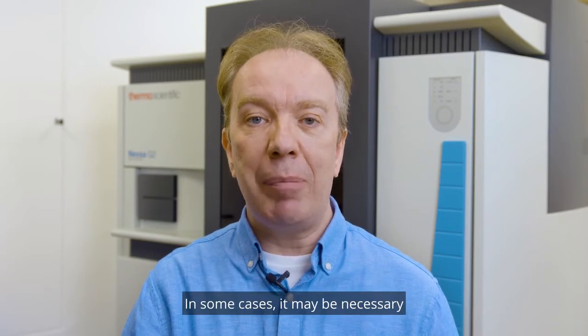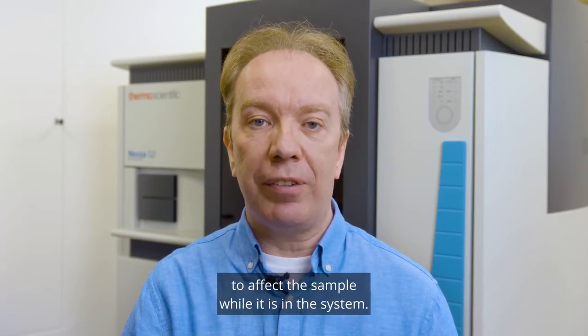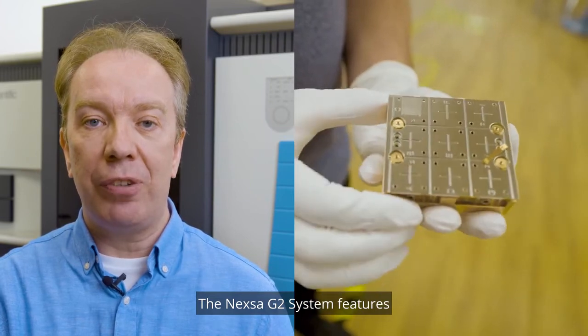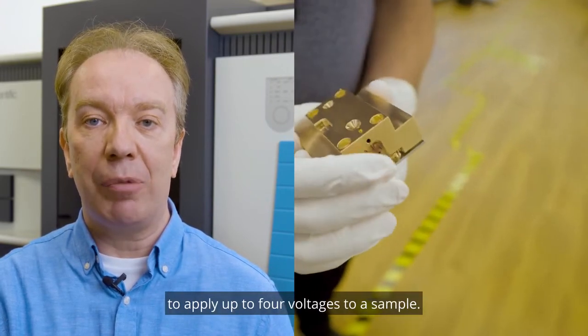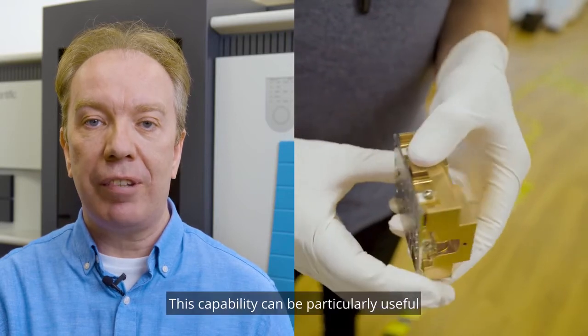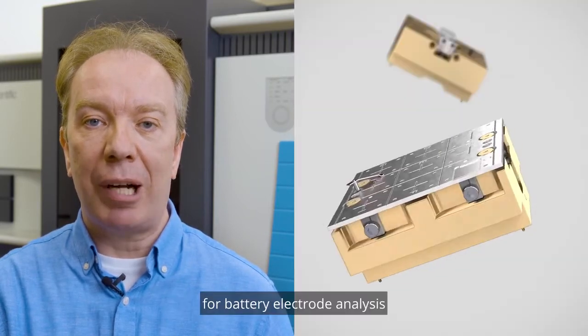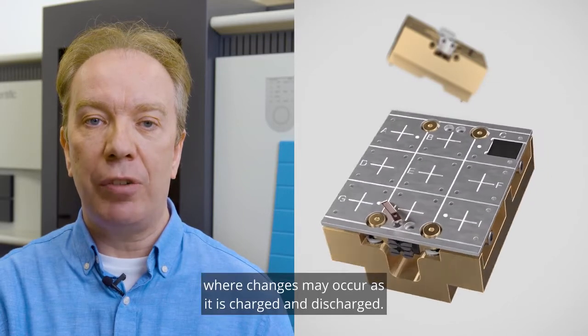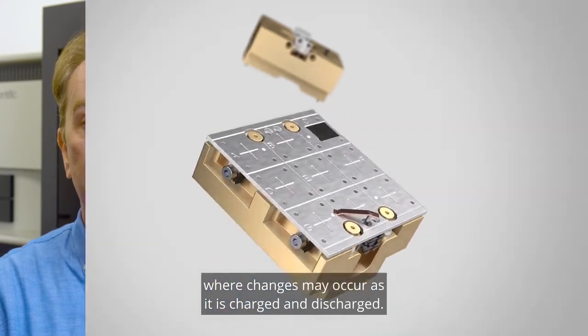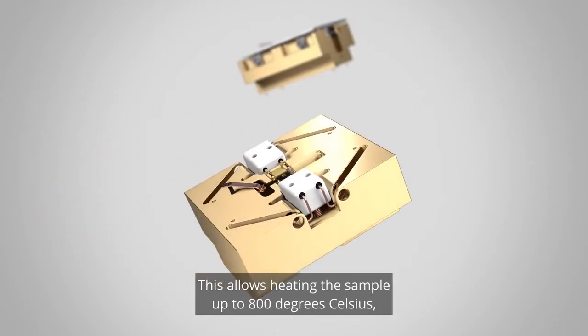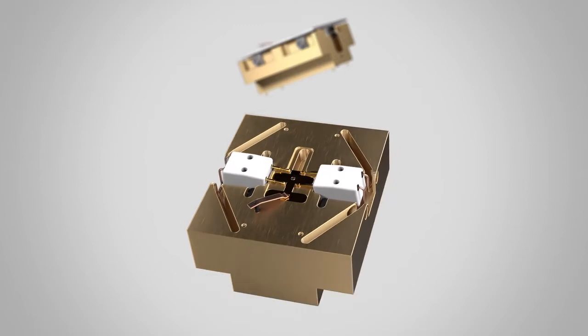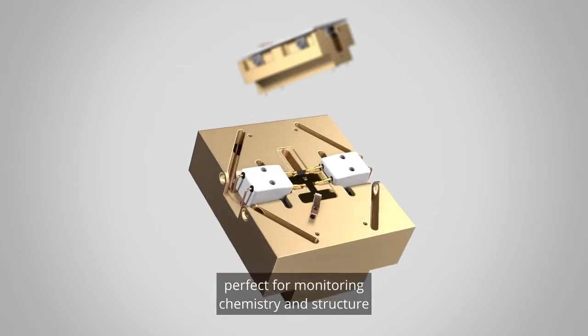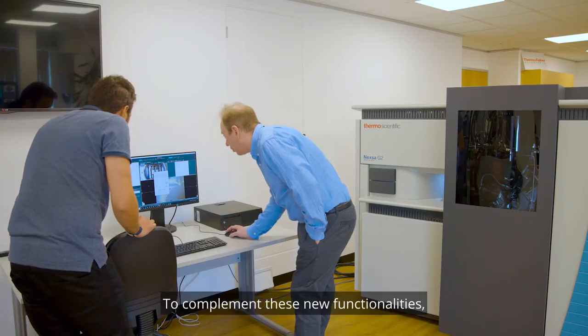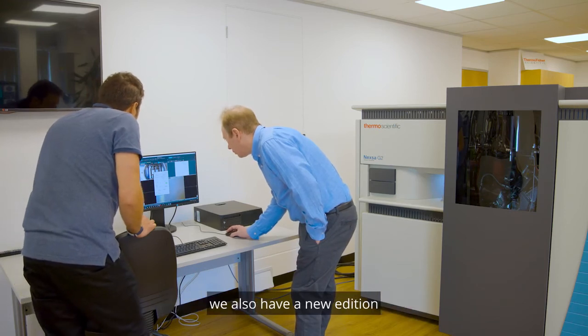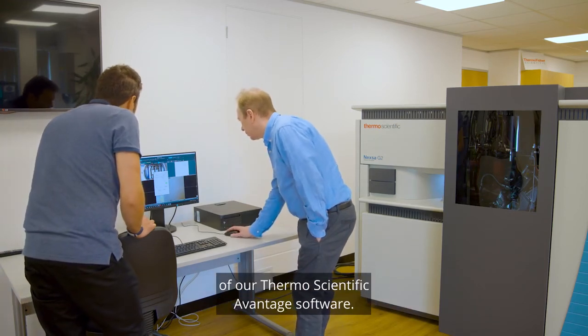In some cases, it may be necessary to affect the sample while it is in the system. The Nexsa G2 system features an optional biasing sample holder to apply up to 4 voltages to a sample. This capability can be particularly useful for battery electrode analysis, where changes may occur as it is charged and discharged. There's also the option for the NX heater with full software control. This allows heating the sample up to 800 degrees Celsius, perfect for monitoring chemistry and structure as they change with temperature.